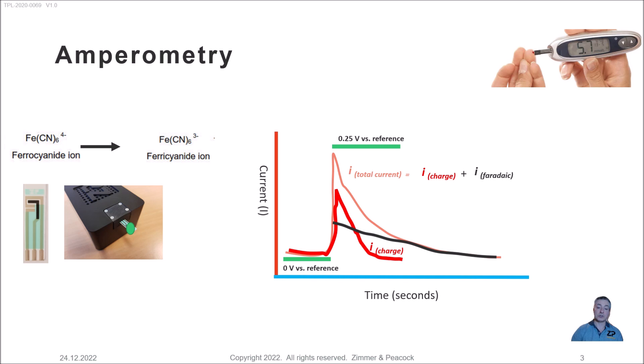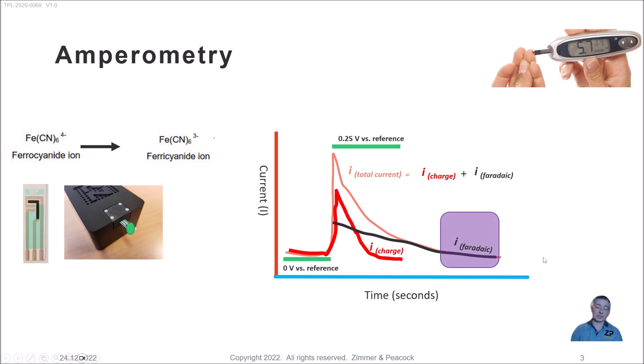A Faradaic current means it's due to an electrochemical process — i.e., the oxidation of ferrocyanide to ferricyanide. A non-Faradaic process is, for example, the rearrangement of ions due to the application of that potential. Charging current is the current due to a change in voltage — the electrode is essentially acting like a capacitor charging up. That's why most glucose strips give a result in about five seconds: you can't measure in one or two milliseconds because a lot of that signal would be non-specific charging current. They wait approximately five seconds to get the specific Faradaic signal.